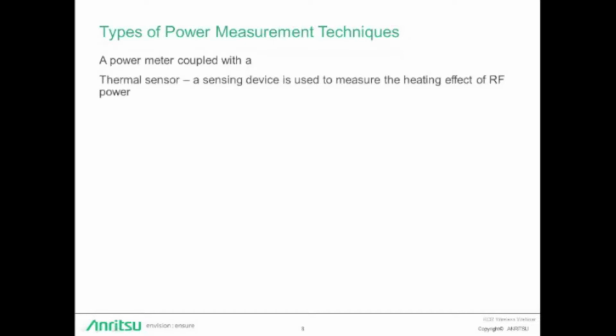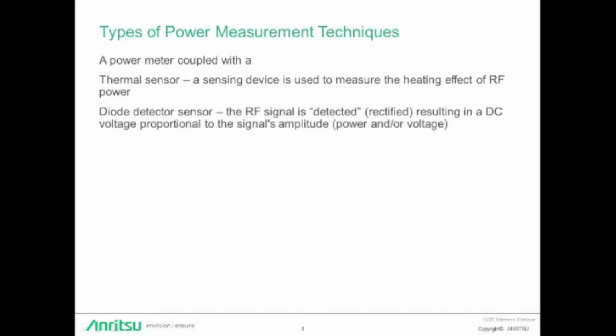A thermal sensor utilizes a sensing device to measure the heating effect of the RF power. And with a diode detector sensor, the RF signal is detected or rectified, resulting in a DC voltage proportional to the signal's amplitude, depending on power level. In the first two techniques, the power is directly sensed. The RF is applied to a load, which converts RF to a DC quantity, which is measured by a meter. The direct sensing approach typically results in the most accurate power measurements.